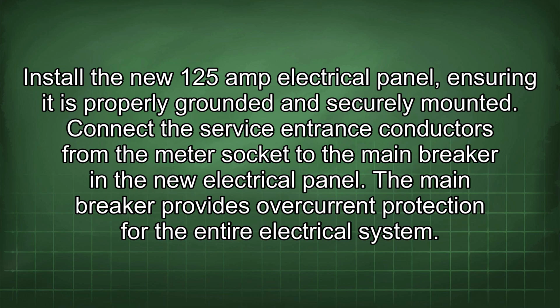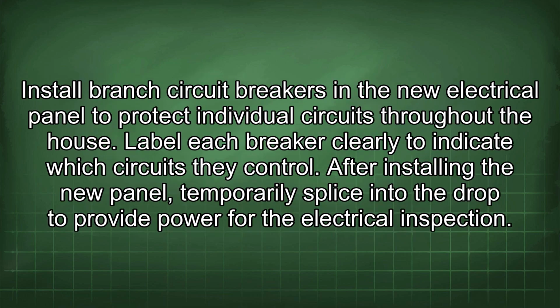Install the new 125-amp electrical panel, ensuring it is properly grounded and securely mounted. Connect the service entrance conductors from the meter socket to the main breaker in the new electrical panel. The main breaker provides overcurrent protection for the entire electrical system. Install branch circuit breakers in the new electrical panel to protect individual circuits throughout the house. Label each breaker clearly to indicate which circuits they control.